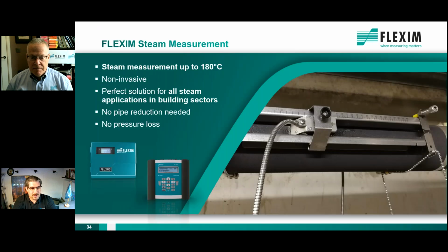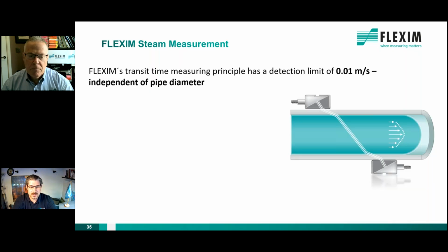So to wrap it up a bit, here is what we can provide. We have steam measurements non-invasively for steam up to 180 degrees C. This means 180 is probably or typically inside the specifications for building steam, so for your heating process and so on. So this would make it a perfect solution for the building sector. You install it non-invasively outside the pipe without any pipe diameter reduction and no pressure loss. So why is that without pipe diameter reduction? Basically this is because of the measuring principle, and this is also valid for every application.